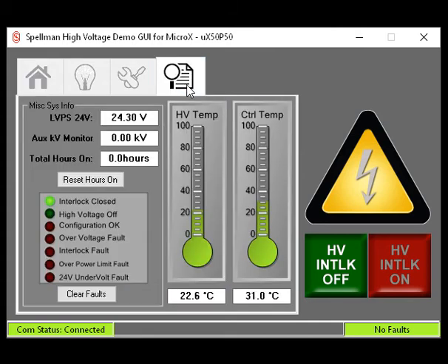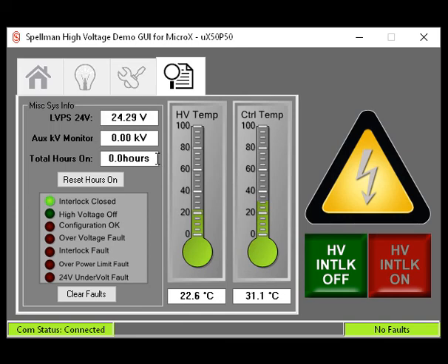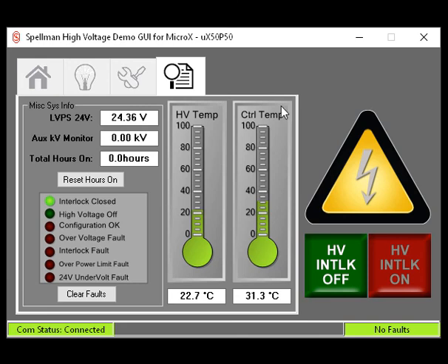The Reporting tab, indicated by the paper and magnifying glass icon, shows a variety of operational information. The voltage of the 24-volt DC power supply providing power to the X-ray generator is displayed. An auxiliary KV monitor displays the high voltage output. The total number of hours on is displayed and can be reset. Interlock status along with several fault conditions are displayed, along with a button used to clear any faults. Two temperature monitors are displayed: one showing the high voltage assembly temperature, the other showing the temperature of the system control board. This concludes our MicroX Demo GUI video. Thank you.